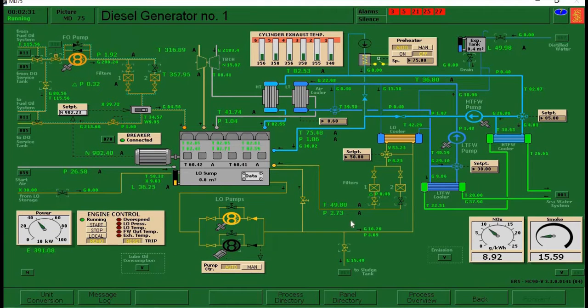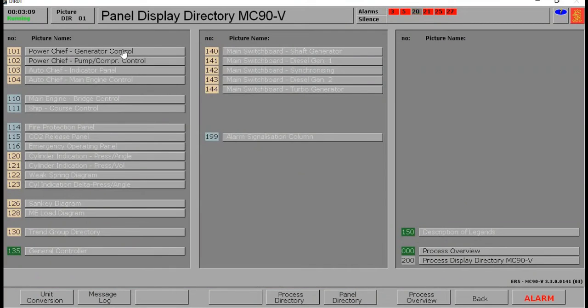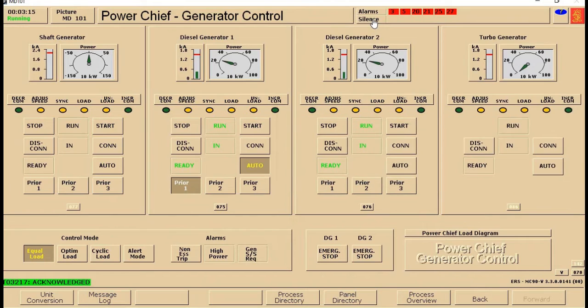Let's check the parameters. So our discharge valve should be closed. Acknowledge the alarm. Okay. Open our makeup valve here, so we can get rid of the low level alarm in our sump. Top up a little bit of lube oil. Then afterwards, we can close this one. Okay, so just silence the alarm. So check the diesel generator 2. It's good. So we'll go to the panel directory, to the generator control. Okay, just acknowledge the alarm.